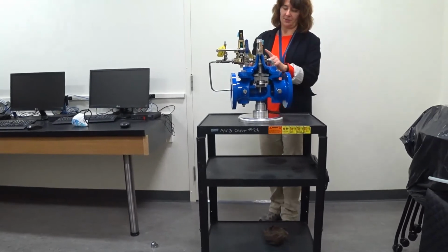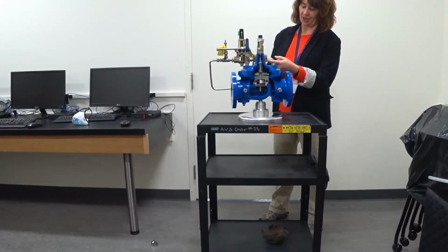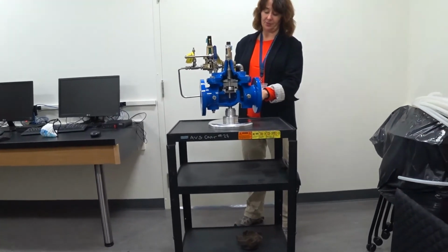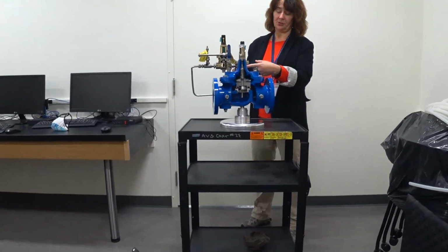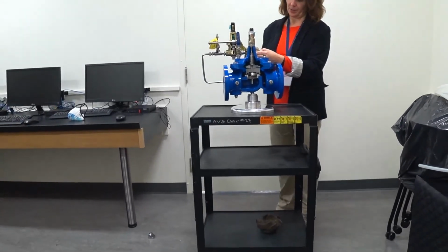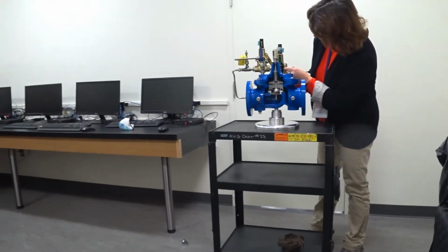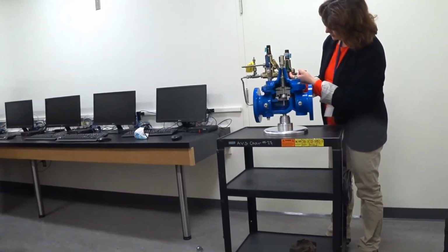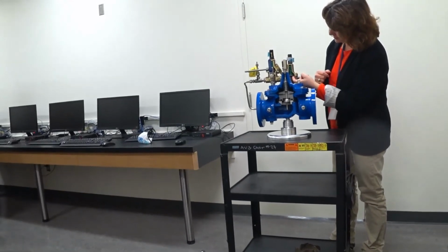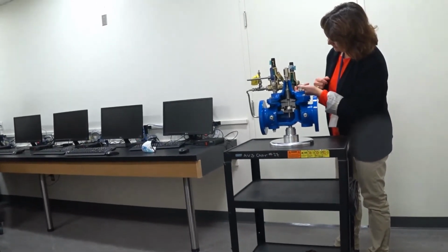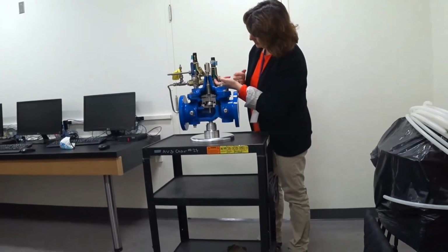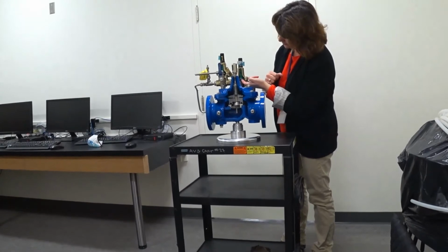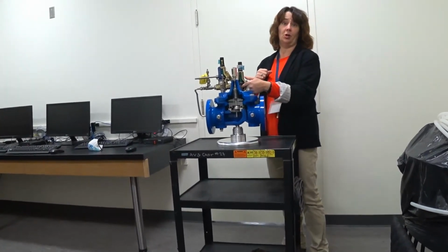So with the CRD, its sensing chamber is the same as the valve chamber itself. So it's set up so that it senses the downstream pressure in its chamber here, and it's a little reverse seated valve. So when you have high pressures on the downstream side, higher than the CRD is set up, it will force the diaphragm up, which causes the stem to go up because it's winning against the spring force, and that will cause this valve to close.